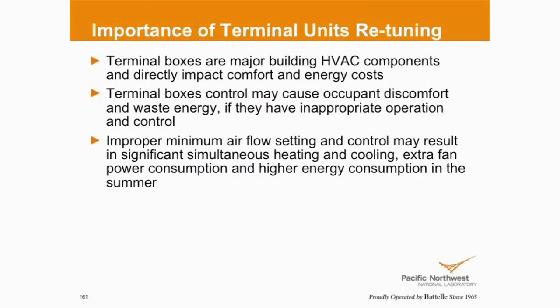Improper minimum airflow settings may result in significant simultaneous heating and cooling, higher fan power consumption, and higher energy consumption in summer. For most control vendors, they set the cooling minimum equal to the heating minimum equal to the heating maximum. That's the default setup. But a lot of energy service providers may provide a better solution for that.